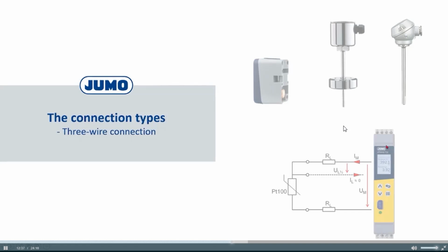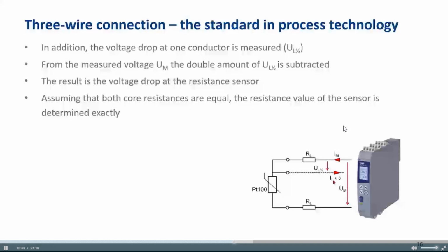If you work with a three-wire connection, then it's much better. Now, if you look at the three-wire connection, you see here, okay, you give your Pt100 to your evaluation unit. Then we give the current through this loop, and we measure the voltage here. But now you see there's a third wire, and now the field device measures this total voltage which drops on the cable and on the Pt100.